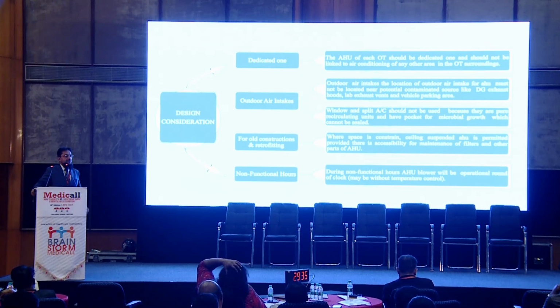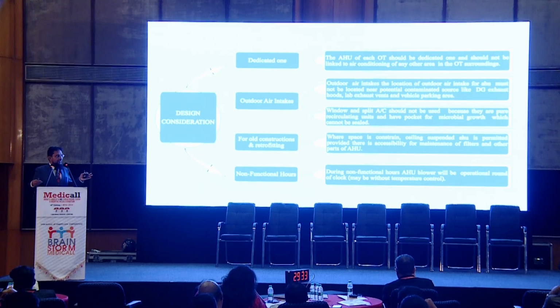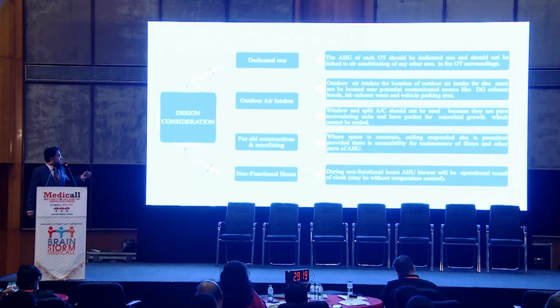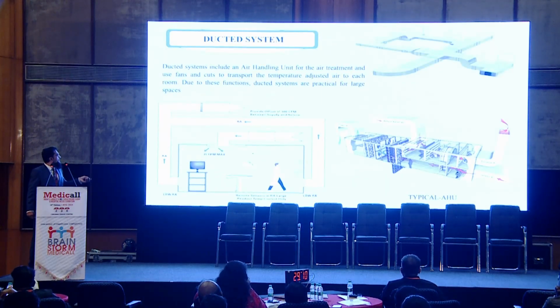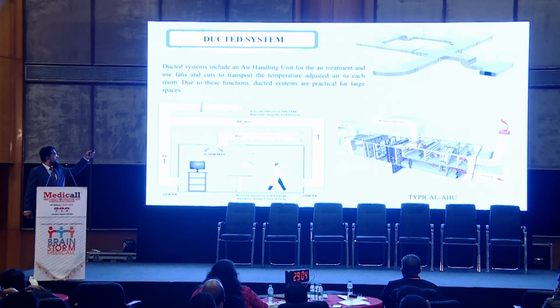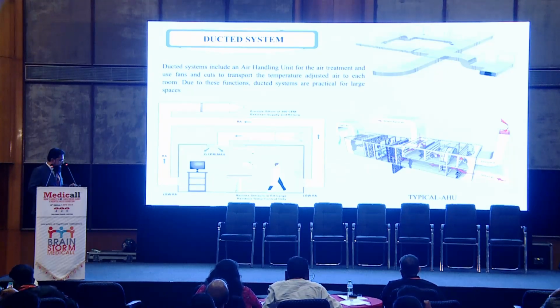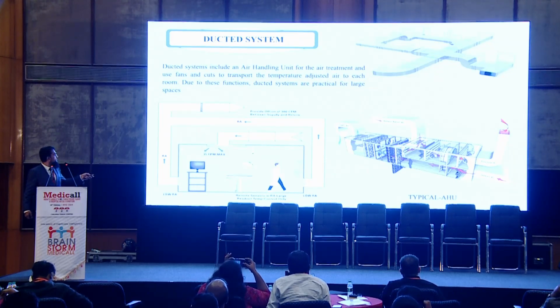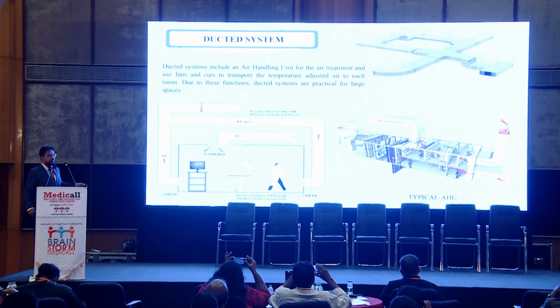See, if you don't maintain it, condensation will happen inside the duct, and there will be tremendous fungus and bacterial growth inside the duct. So, to avoid the condensation and the fungus and bacterial growth inside the duct, they said that during the non-functioning hours, you have to maintain the flow inside the duct. You know the ducted system, how it looks, what the flow is. Normally you can see this is the ceiling, then these are the return ducts, and the AHU is here.